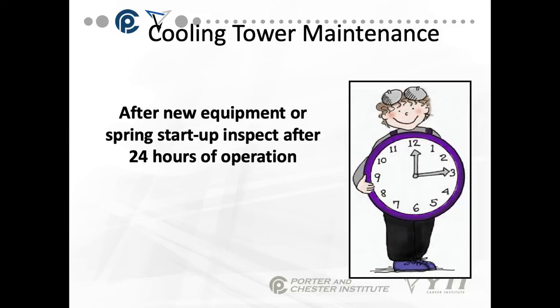So, the biggest issue with cooling towers is proper maintenance. After new equipment or spring startup, it needs to be inspected after 24 hours of operation. We're looking for leaks. We're looking for signs of wear and tear. We're looking for water not running properly down the panels.